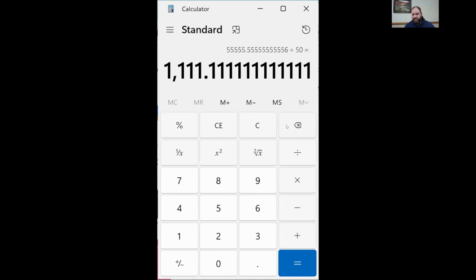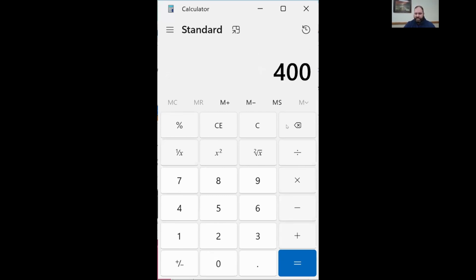Now, if I take the same 60,000 BTU load and apply a heat pump to it, I need to move 400 CFM per ton. So 400 CFM times, 60,000 BTUs divided by 12,000 is 5. So this is a 5-ton load. So I need to move 2,000 CFM. So I need to move almost double the CFM.